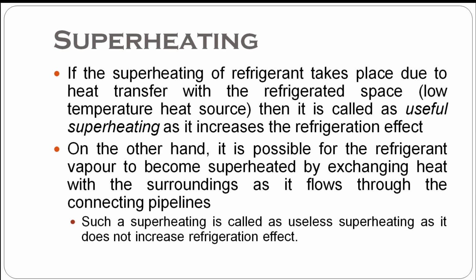If this superheating of the refrigerant takes place due to heat transfer with the refrigerated space, that is, the low temperature heat source where the space is to be cooled, then it is called useful superheating, as it increases the refrigeration effect. If an additional amount of heat is removed from the space to be cooled, so that the saturated vapor refrigerant is superheated, that is useful superheating. On the other hand, it is possible for the refrigerant vapor to become superheated by exchanging heat with the surroundings as it flows through the connecting pipelines between the evaporator and compressor. If that happens, that is useless superheating. It does not increase any refrigeration effect, right? So there are two kinds of superheating: useful superheating and useless superheating.